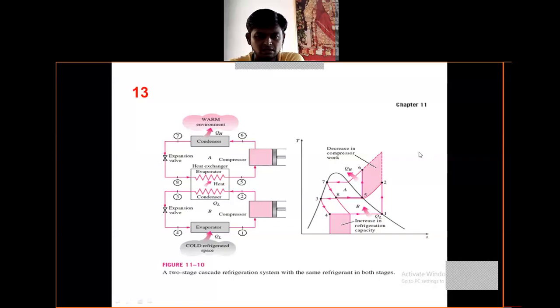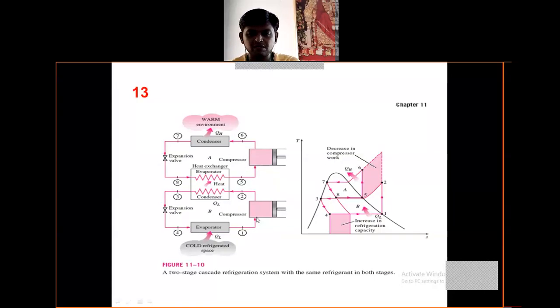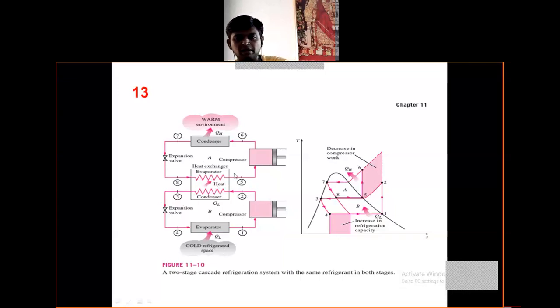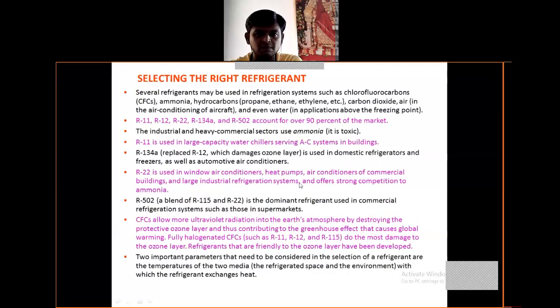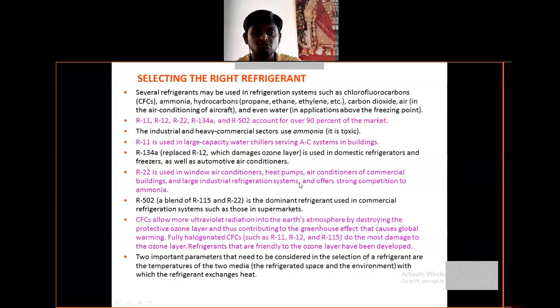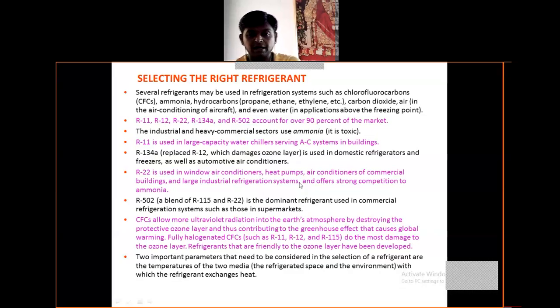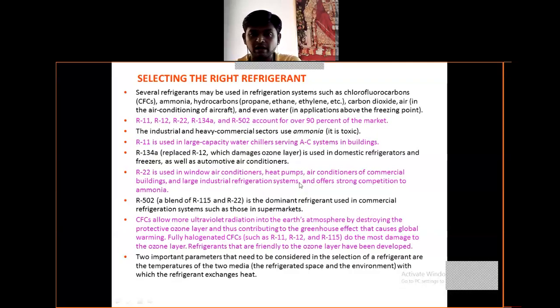This is a two-stage cascade refrigeration system with the same refrigerant in both stages. You can also have two refrigerants working together in a combined cascade system with two stages and two refrigerants. Refrigerant options include CFC (chlorofluorocarbon), ammonia, hydrocarbons like propane and ethylene, carbon dioxide, air (for aircraft air conditioning), and even water.